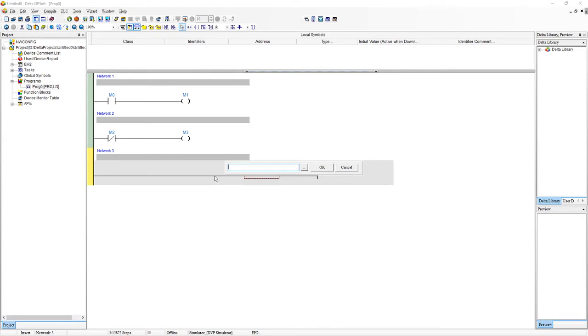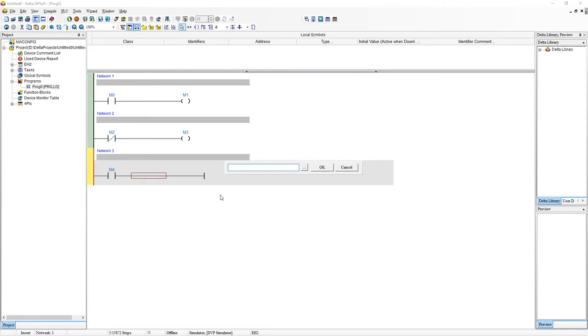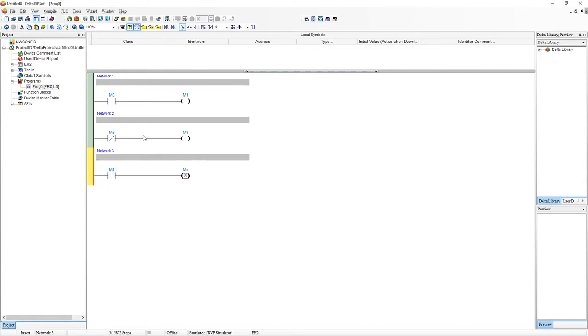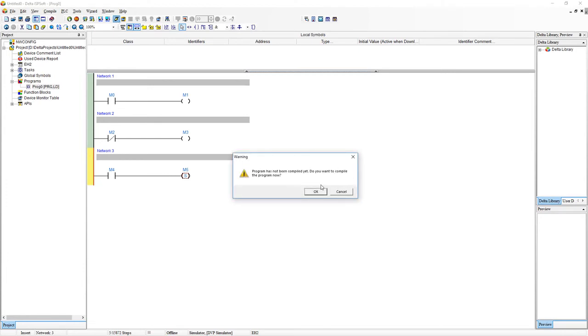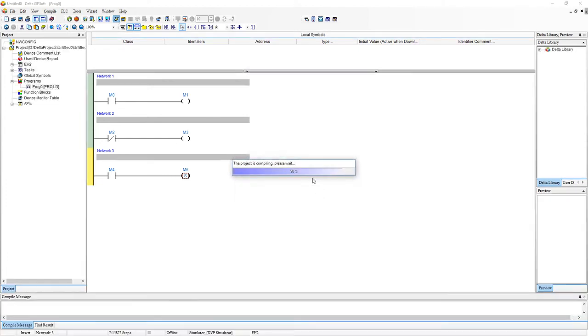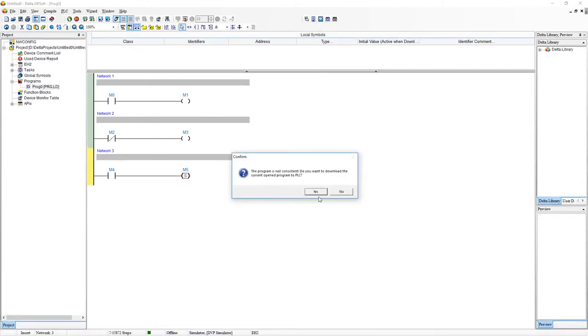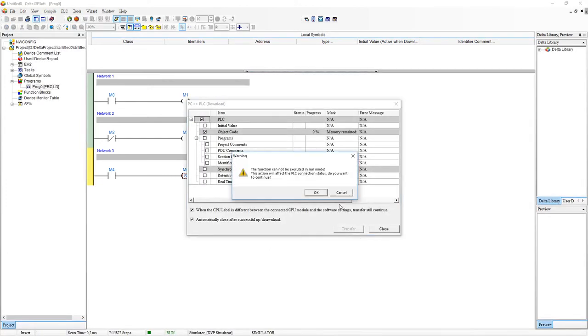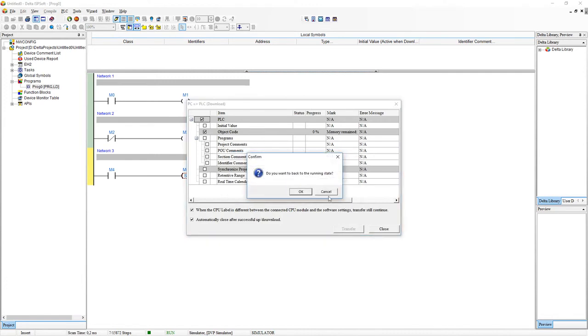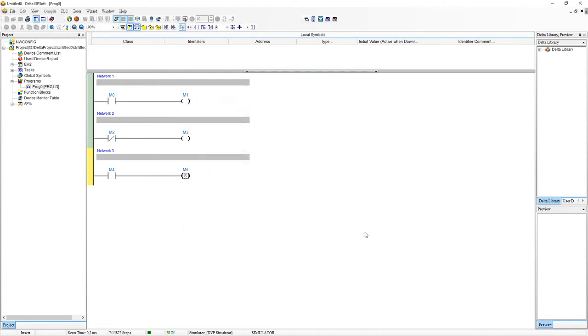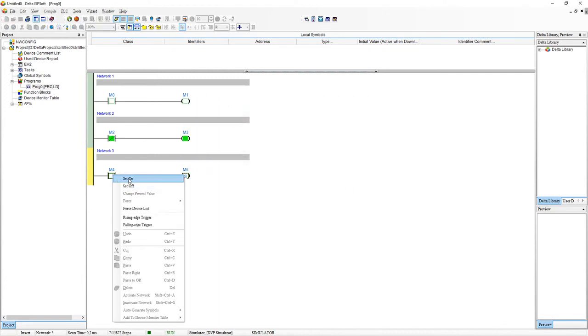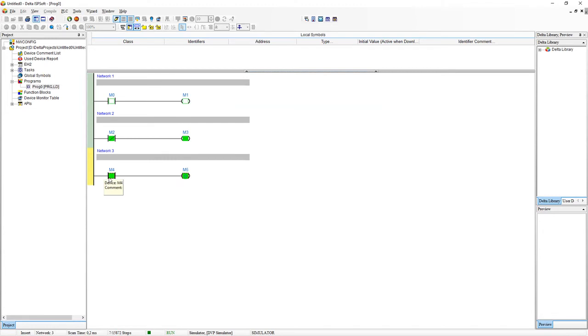So just for this example we're going to use LD M4. And again hit space bar we're going to say SET M5. So the SET will basically persist M5 when M4 is turned on. So just to prove that concept let's go back into online mode. So yes. OK. OK. So turn M4 on. And turn it off. And you'll see that M5 stays on.